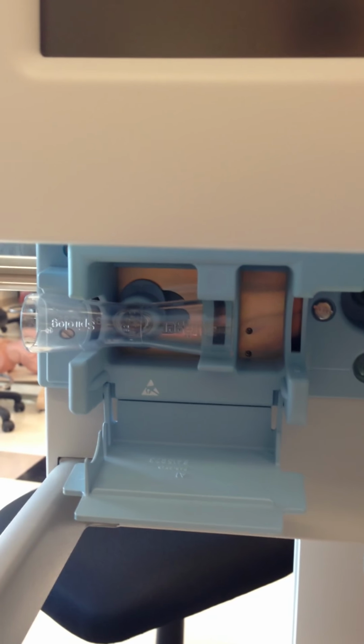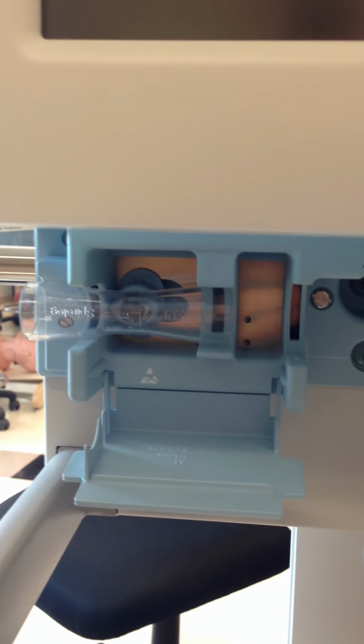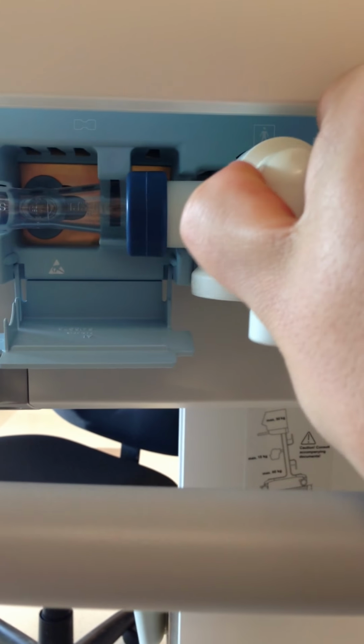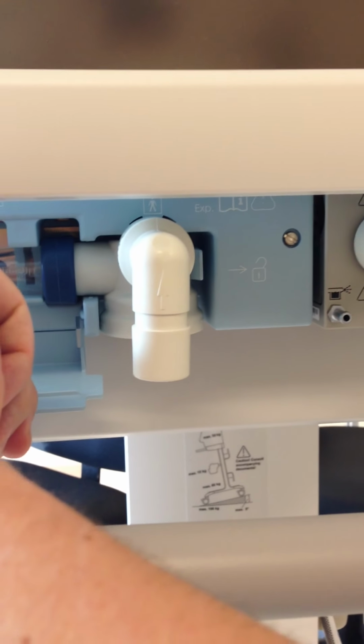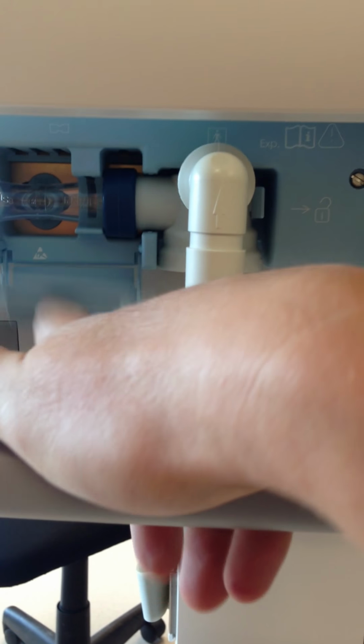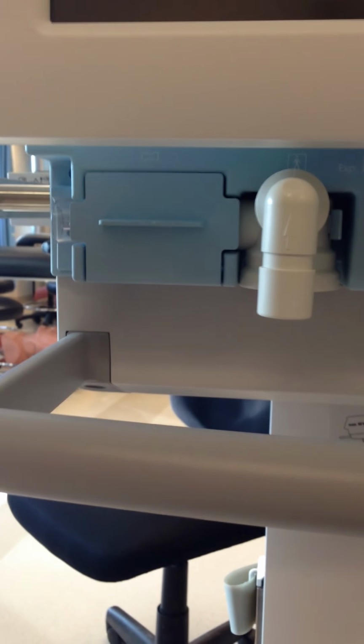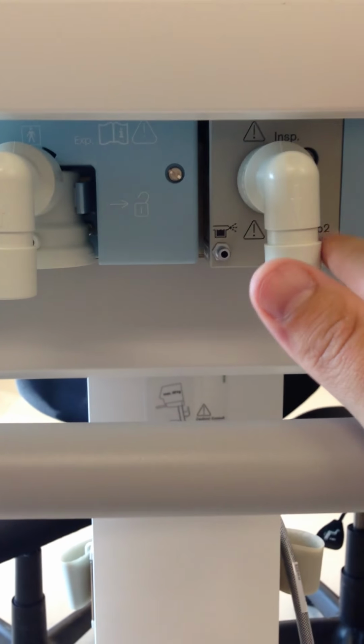Okay, so first off, let's get the expiratory valve and flow sensor assembled down into the expiratory inlet. So here's the inspiratory, this will be the expiratory. You can see I popped in the flow sensor. I'm going to take my expiratory cartridge, or the assembly now, and insert that in. You're going to then push your flow sensor back over. It's on a slide. There's a little catch here for the expiratory, so just make sure it's snug. Then you can close up that door, and that's assembled for the Draeger Evita XL, inspiratory, expiratory.